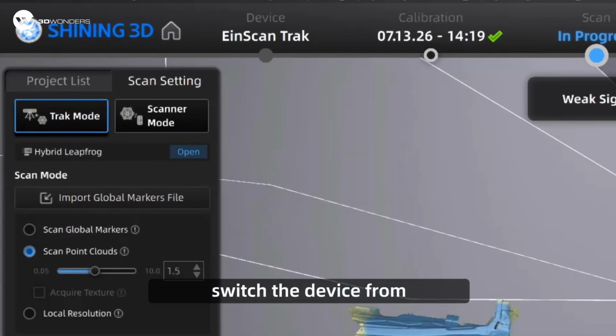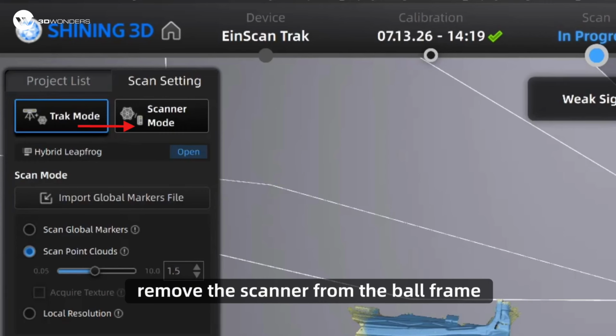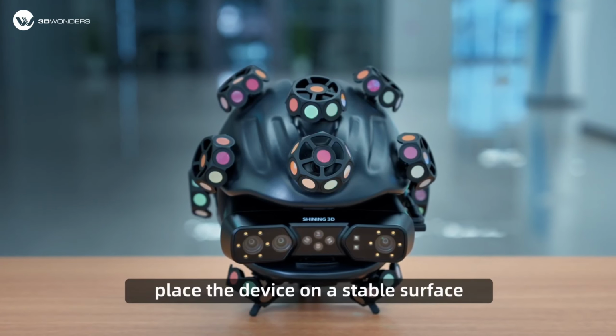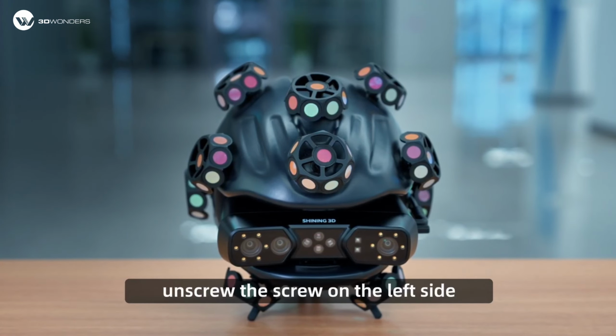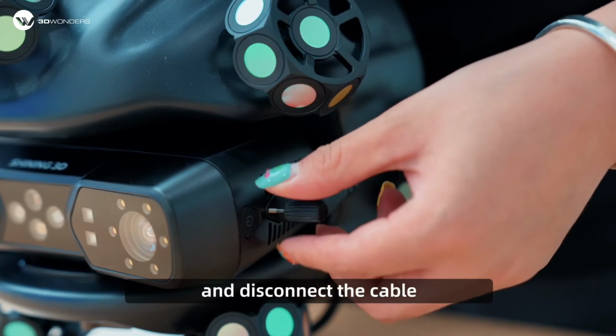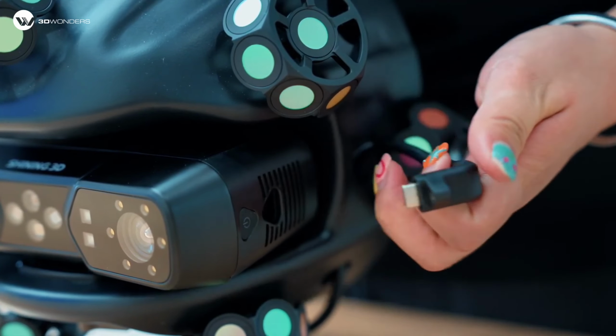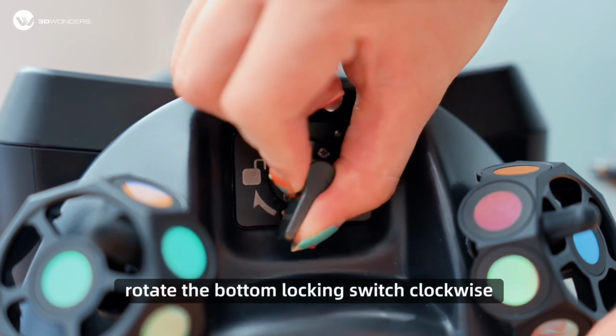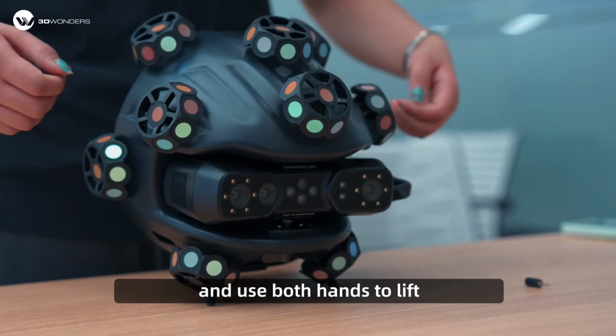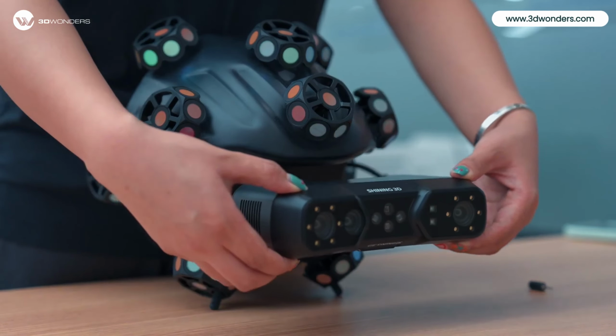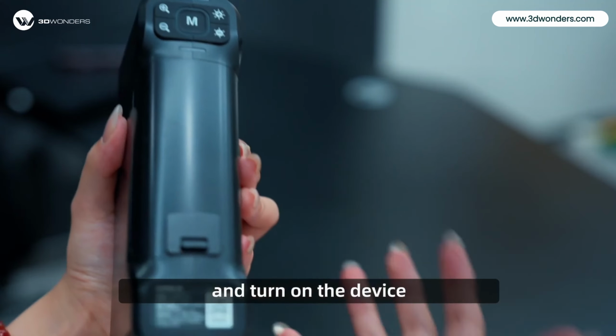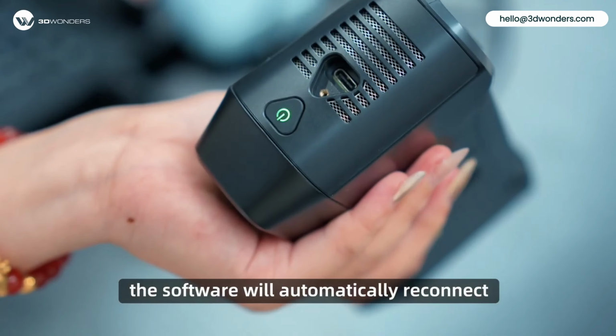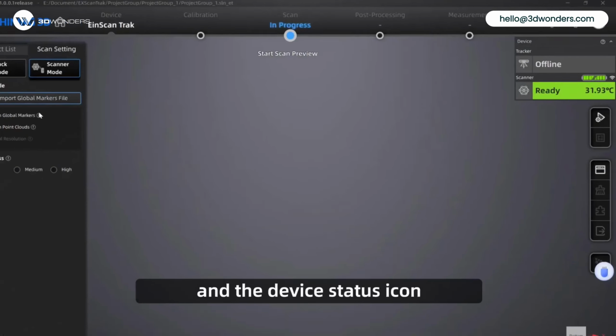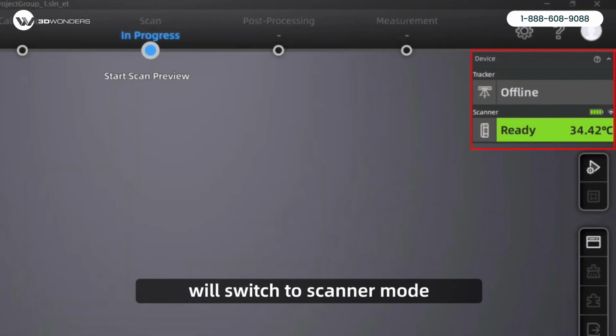First, switch the device from Trak mode to scanner mode. In the software, you can start the scanning directly. You can also choose to remove the scanner from the ball frame. First, place the device on a stable surface, unscrew the screw on the left side, and disconnect the cable connecting it to the cage. Then, rotate the bottom locking switch clockwise and use both hands to lift the scanner out of the ball frame. Insert the battery and turn on the device. After a few seconds, the software will automatically reconnect, and the device status icon will switch to scanner mode.